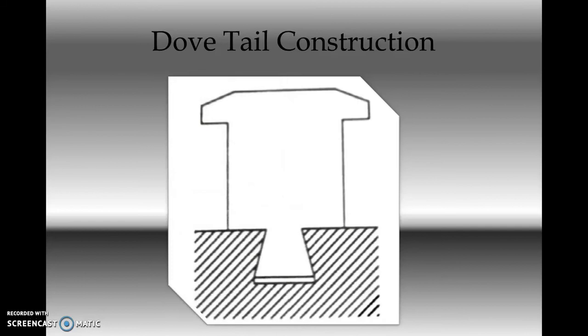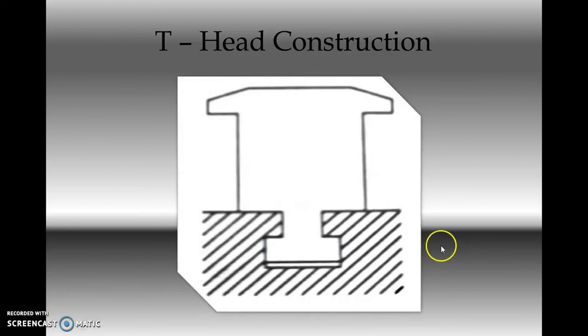For higher speed, we go for dovetail type of construction. In this type, the pole is housed or embedded in the outer periphery of the rotor yoke and the shape is like a dovetail. For even higher peripheral speed, we have T-head type of construction. It is a similar type of construction, but the shape embedded in the rotor core outer side is different — the shape is like an inverted T-head. Compared to dovetail, T-head is more useful for higher speed.